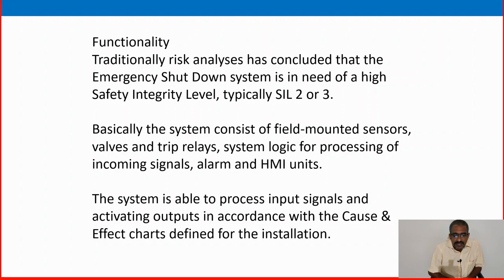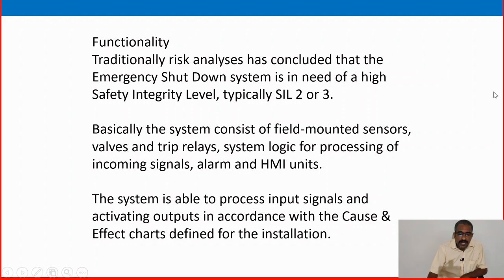Basically, the system consists of field-mounted sensors, valves, and trip relays, system logic for processing of incoming signals, alarm and HMI — that is, human-machine interface units. The system is able to process input signals and activate outputs in accordance with the cause-and-effect chart defined for the installation.